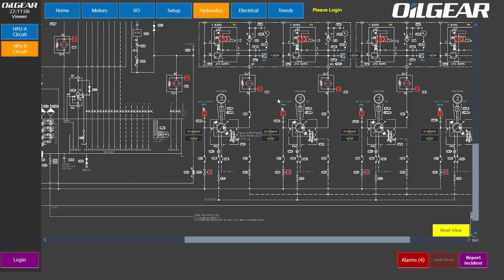in reality, you could stop there and just have it so that at least the person has the circuit on the screens. But then, if you want to make a mimic screen, you can drop all the animated red and green circles and whatnot, squares. So that's half an hour's work, an hour's work to get the circuit on the screen, and then a week of tagging it up, depending on how much IO you got. 2-3 days to a week to 2 weeks.